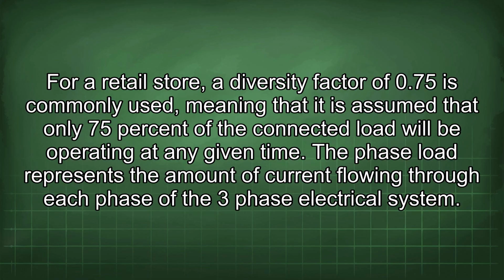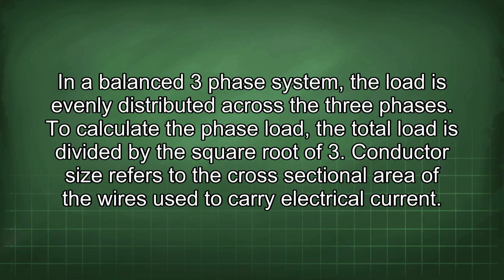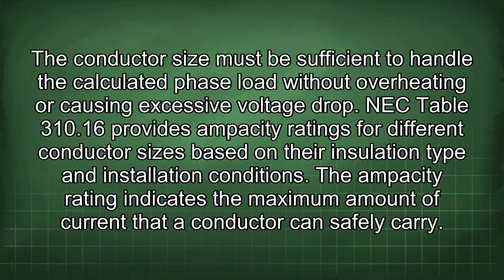The phase load represents the amount of current flowing through each phase of the 3-phase electrical system. In a balanced 3-phase system, the load is evenly distributed across the 3 phases. To calculate the phase load, the total load is divided by the square root of 3. Conductor size refers to the cross-sectional area of the wires used to carry electrical current. The conductor size must be sufficient to handle the calculated phase load without overheating or causing excessive voltage drop. NEC Table 310.16 provides ampacity ratings for different conductor sizes based on their insulation type and installation conditions. The ampacity rating indicates the maximum amount of current that a conductor can safely carry.